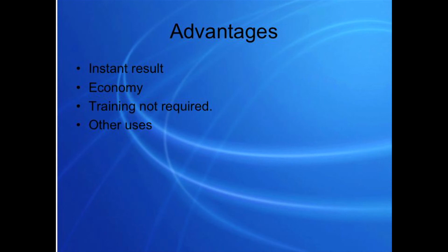Also, there will be no training required to use that program because it will be very easily seen. If there's helium present, you know there's a leakage because the helium gas will be leaking through wherever the leak is. And by just seeing that light coming out from our module, from the photomultiplier, you know that there's a leak. Or if there's not a leak, then you won't see the light. And that's pretty much our product.